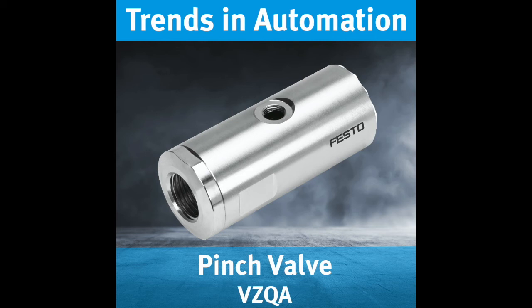One of the biggest limitations for our pinch valve is that it can only be used with relatively low pressure. Our normally open version can only handle up to 60 psi line pressure, while the normally closed can go up to 90 psi. When it comes to filling and dosing, most of these applications are gravity fed or use minimal amounts of pressure, which again allows our pinch valve to be a perfect fit. But beyond these examples, it's always important to be cognizant of the maximum allowable operating pressure of these valves.